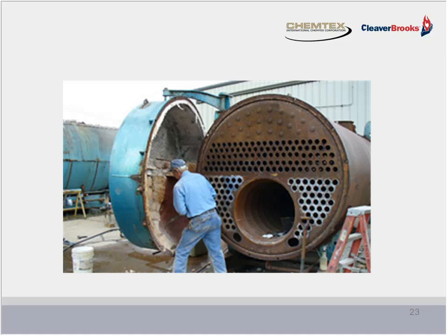Then you have the other costly problem when you have a leaking boiler, and that is the damage to the door's insulating refractory, which got wet, the water turned to steam and expanded, causing large cracks and chunks of this refractory to fall out, meaning the refractory had to be replaced or repaired, and maybe the door had to be replaced too because of overheating and then resultant warping. Thousands of additional dollars are therefore added to the repair.